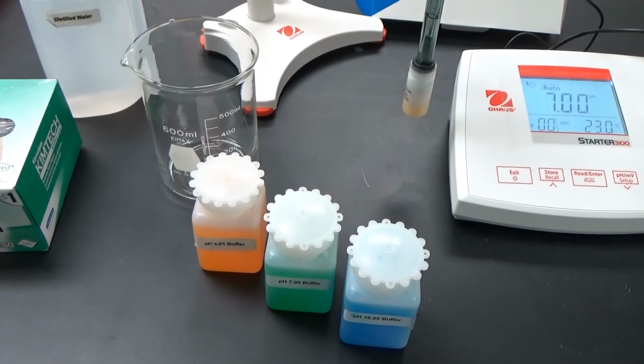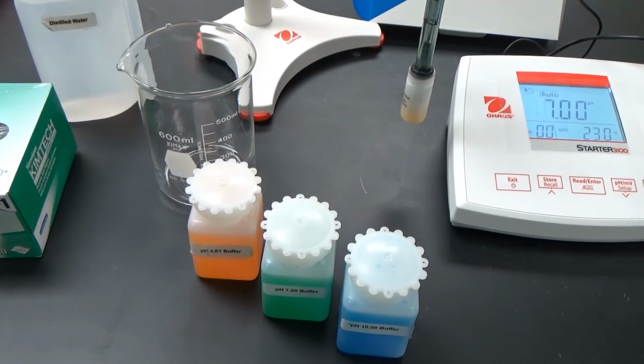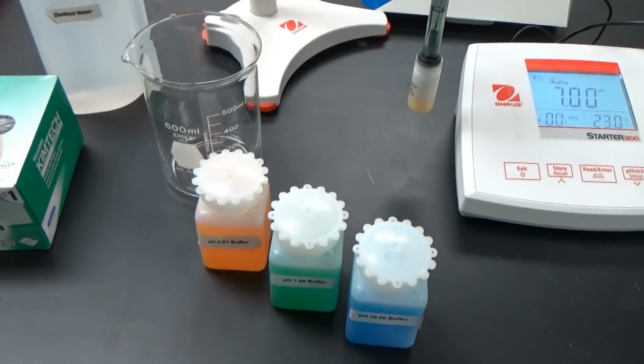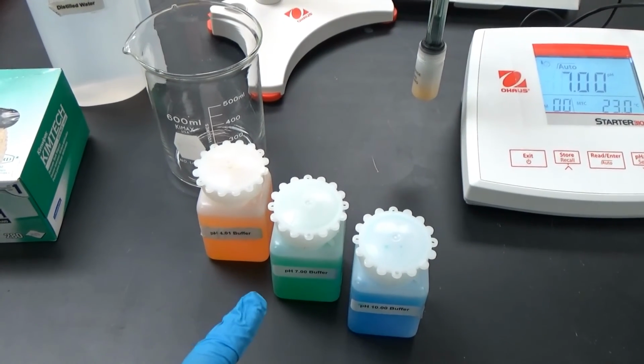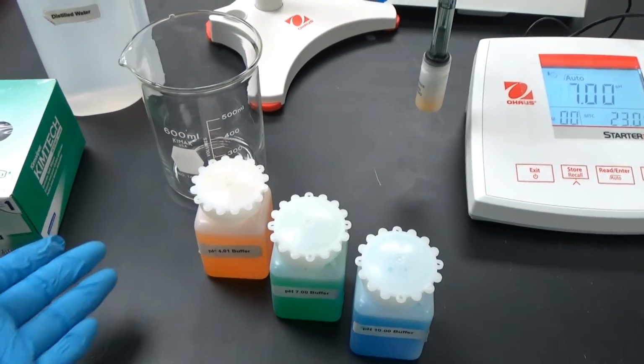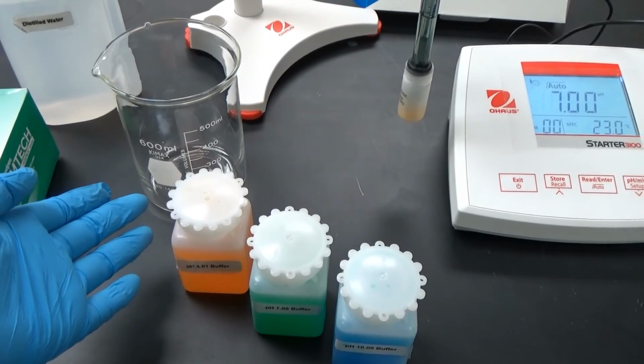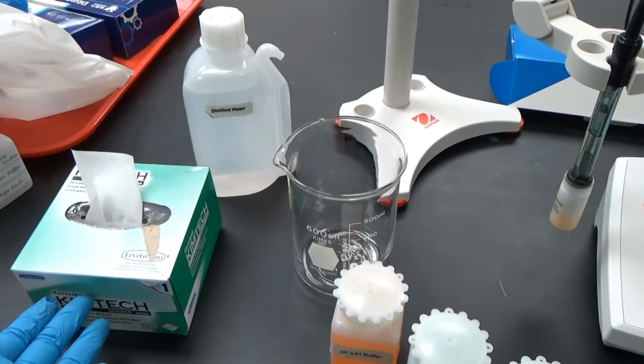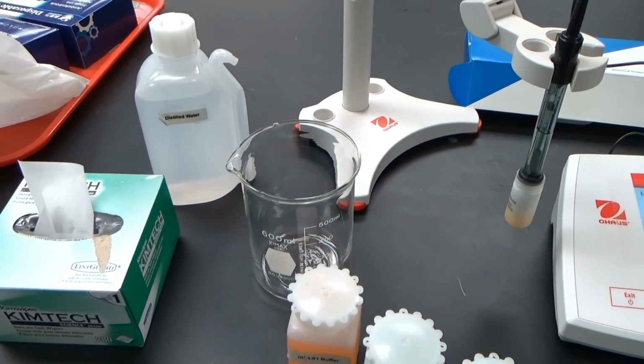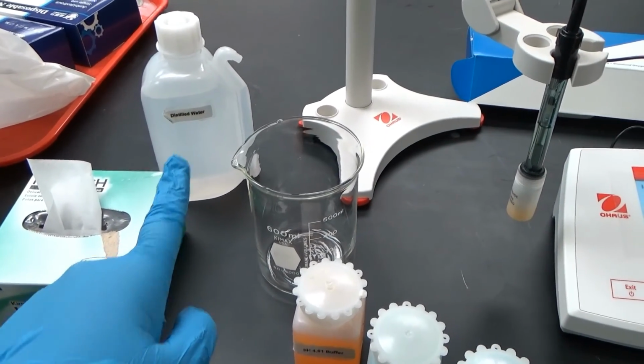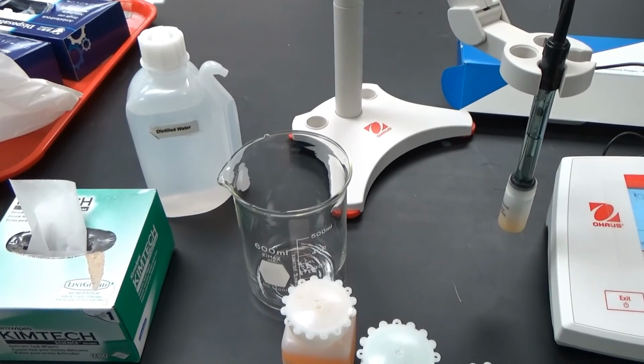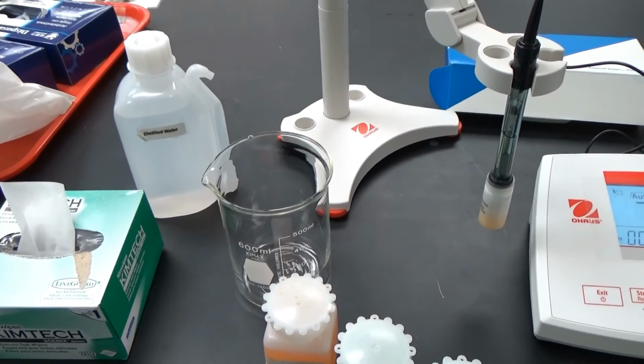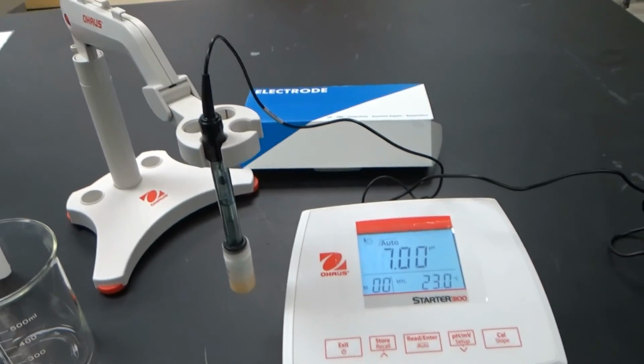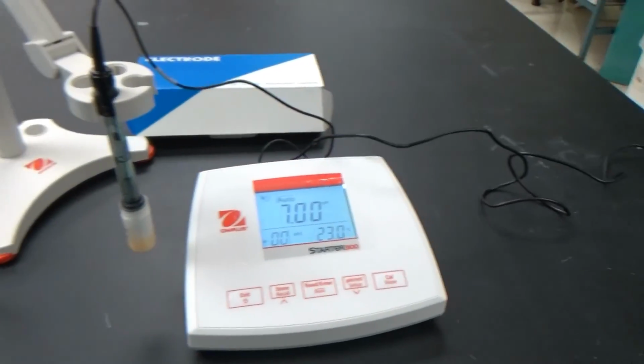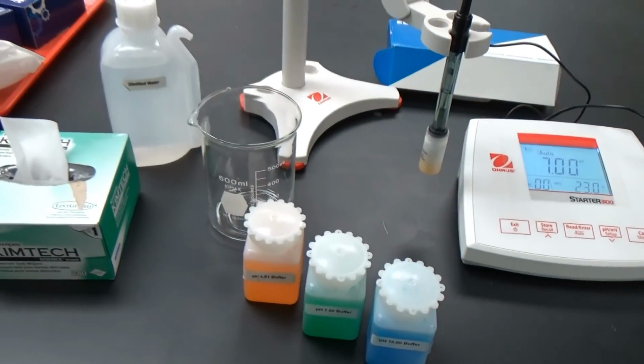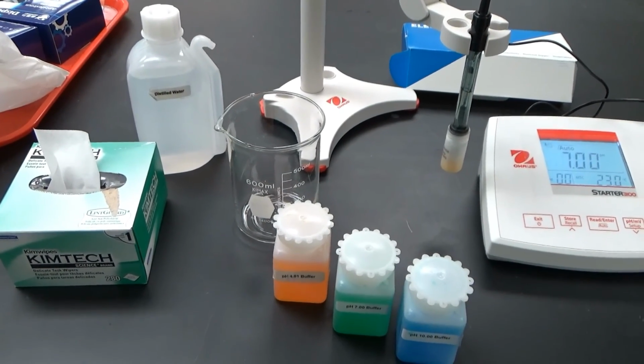For the calibration of the pH meter, 3-point calibration, you will need the 3 buffers, pH 4, pH 7, and pH 10. You will need a waste beaker, preferably a large one, some Kim wipes to wipe off your electrode, some distilled water in a bottle. Make sure there's plenty to rinse your electrode during the whole calibration. And of course, you want to set up your pH meter before you begin. And I will now begin the stepwise explanation.